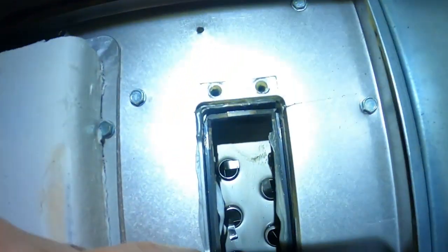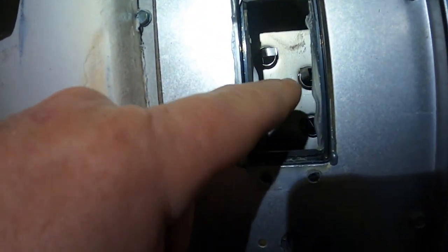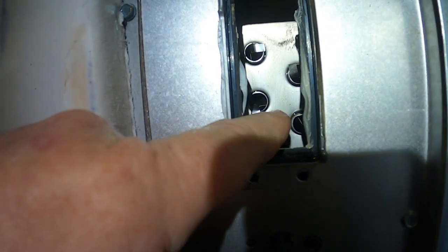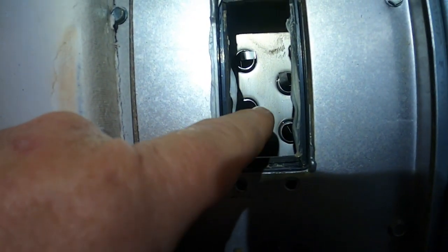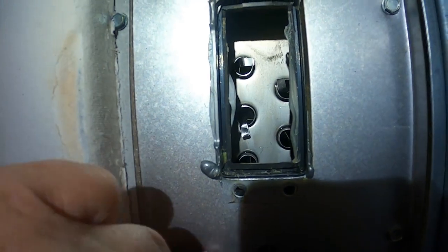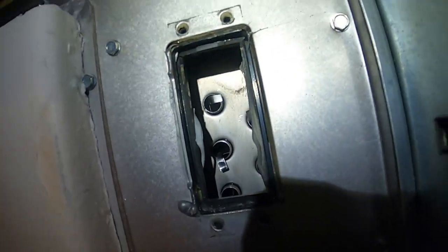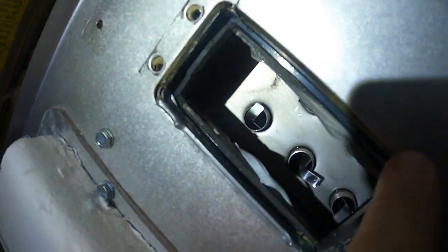If you look right here, there's the secondary heat exchanger for the 90% furnace, and the header on the end of this thing is plastic. What happens to it over time is, if you look right up there, real close, see how that's wiggling and moving? It's cracked. So these things crack, and then you get water and condensation that runs down the inside and does this.